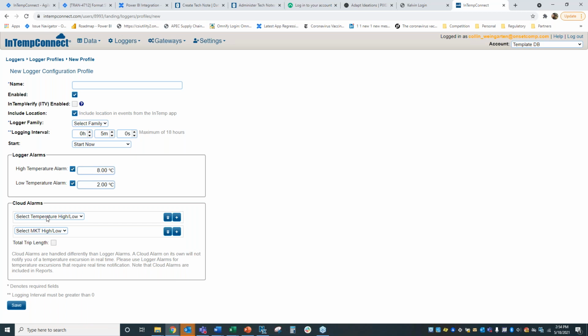The cloud alarms are really for additional reporting. You can set up as many cloud alarms as you want, but usually what I recommend is make these as warning alarms, so they're just warning you that temperatures are about to exceed the absolute limits of that particular product. So when you get the notification, you can look in the report and see, okay, did it exceed the cloud alarm, which is its true threshold? So again, this is what works with your notifications - just for additional reporting, and also allows you to set MKT, mean kinetic temperature, for transportation customers.